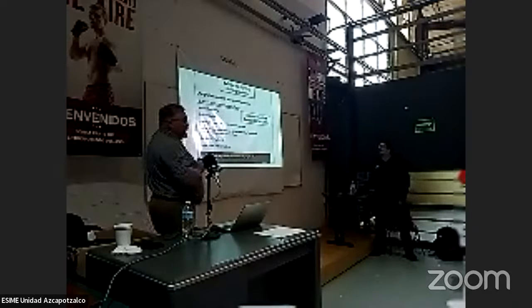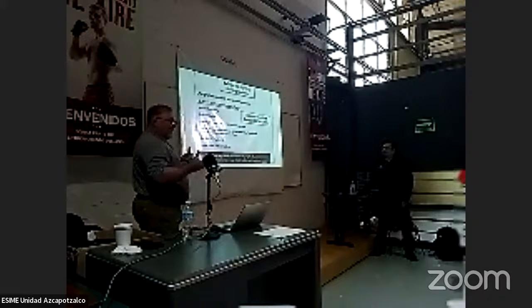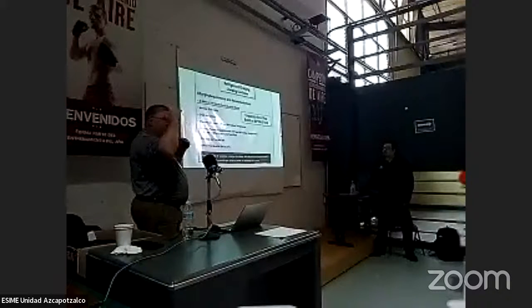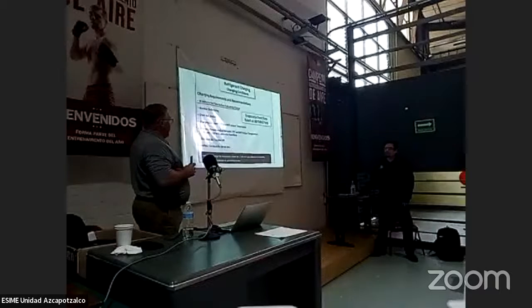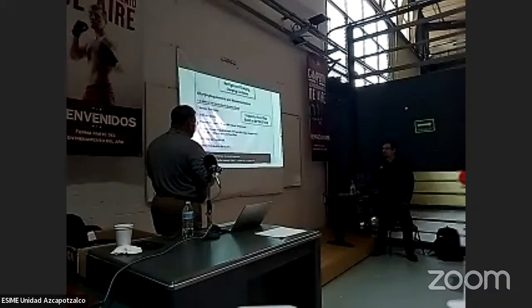So before you start to charge the system, you must let it run for 30 minutes. Okay? This lets everything settle out. It gives the EEVs time to get to the right positions. Once you start doing that, you're going to start monitoring subcooling. You want to check your wet bulb delta T across your evaporator. Charging between 70 and 80 degrees indoor temperature. Charging recommended between 74 and 80 indoor temperature. Most closely matches the evaporator feed. So that's why you want to do that.